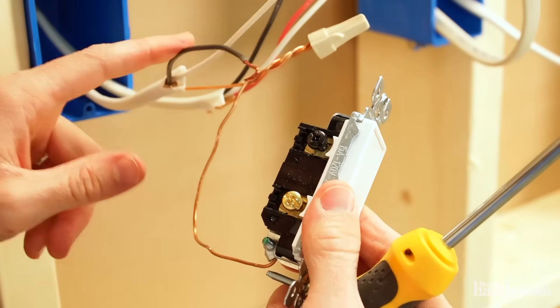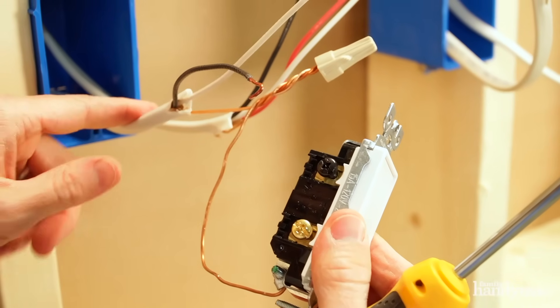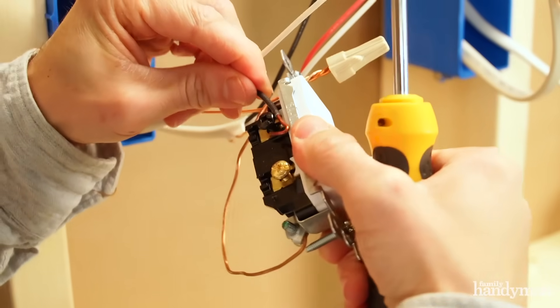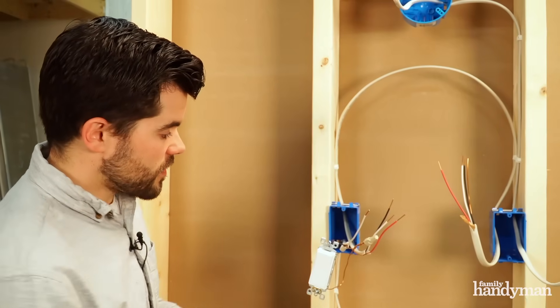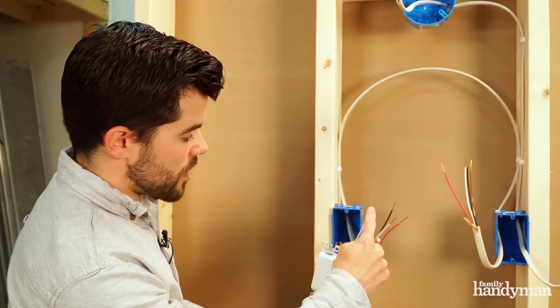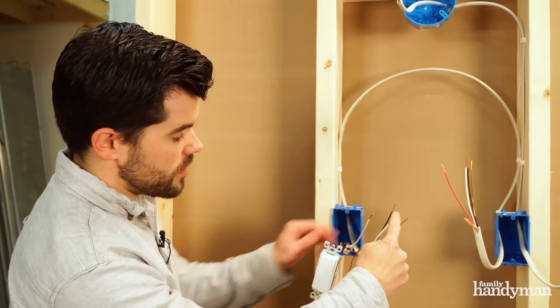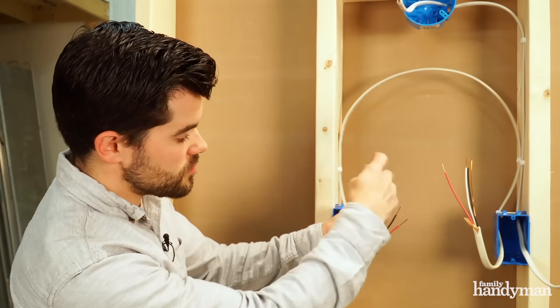Then attach the black wire from the power coming in to the common terminal. Now you're going to connect the neutral wire from the power coming in to the neutral wire in the common cable between the two switches.